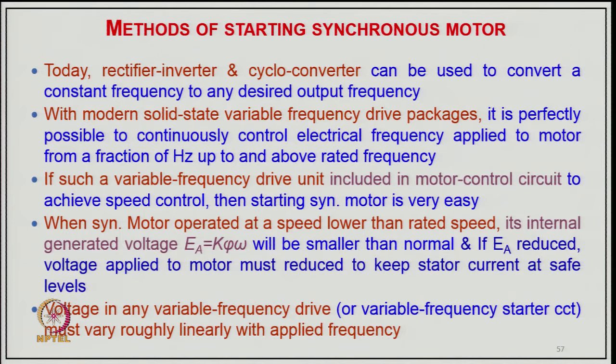With the modern solid state variable frequency drive package, it is perfectly possible to continuously control the electrical frequency applied to the motor from a fraction of a hertz up to above the rated frequency. Such a variable frequency drive unit included in the motor control circuit achieves the speed control. Thus, starting of a synchronous motor is very easy.